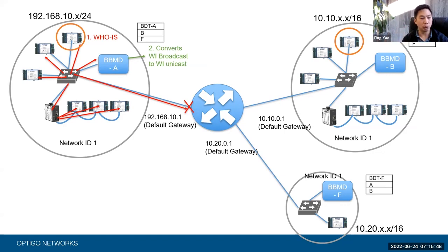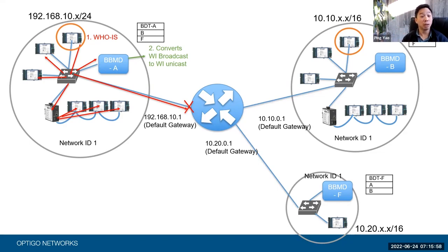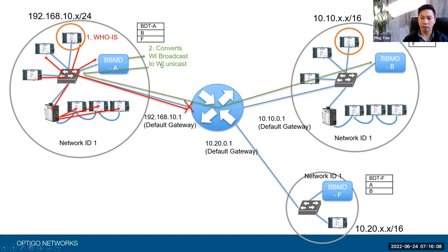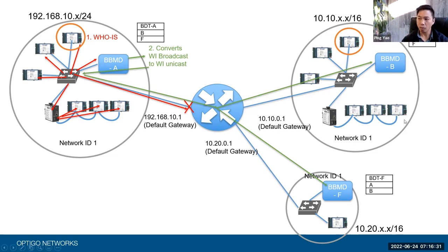These are predefined. You, as a user, as a programmer, as configuration — you have to define these things. So it looks at the BDT and sees it has two entries. It's going to create two unicast WhoIs messages and send them directly to those BBMDs. It converts it and sends it directly to B, and because it's unicast, it goes through the IP router. The second one is the same, sent to F. It sent two unicast messages: one to B, one to F.